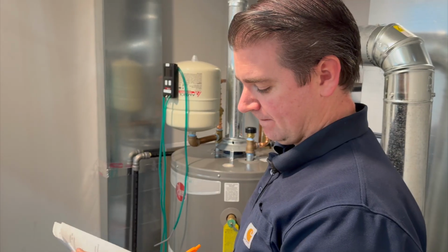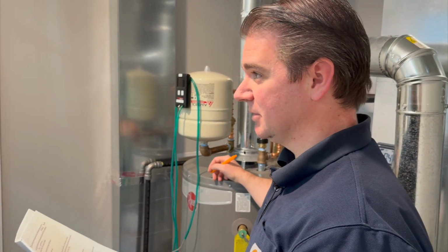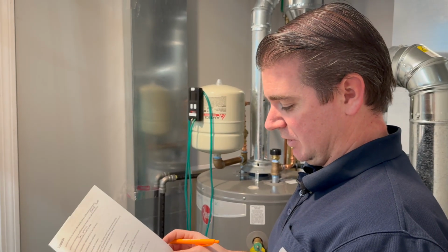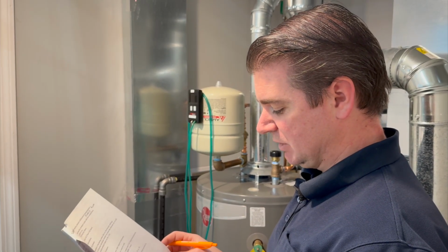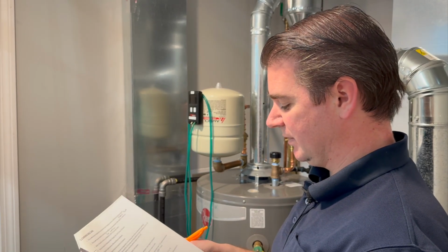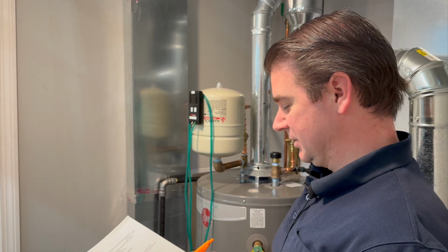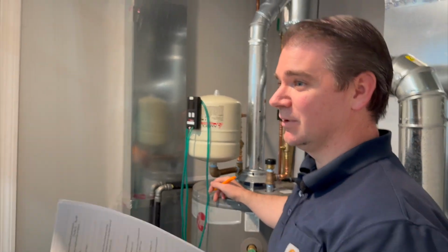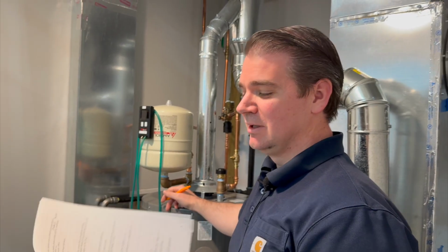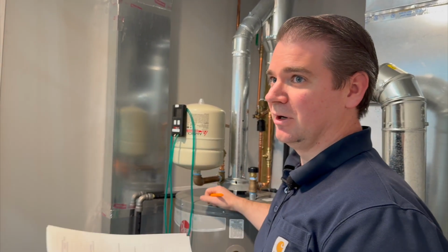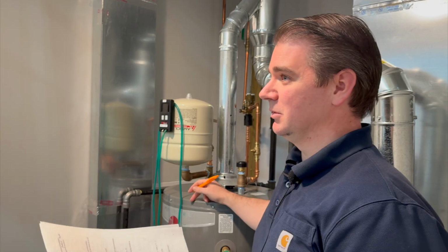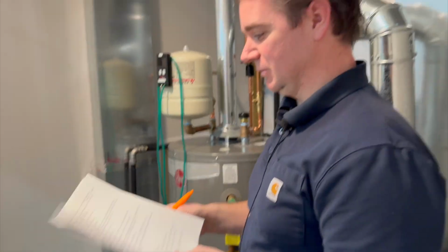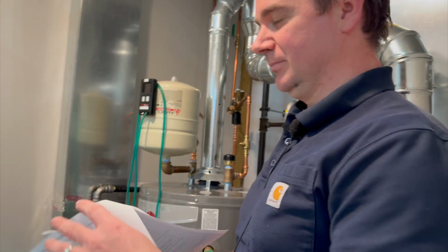And then number 10, discuss 3 potential sources of carbon monoxide in the home: water heater, furnace, oven. We already did number 2, 3, and 4. And discuss the procedure for measuring carbon monoxide in direct vented and power vented combustion appliances. So that would be with a PVC vent, right? That's going to go to the outside of the home. So if I can safely access where the vent terminates for the combustion analyzer, I'll just stick the probe right down the flue vent. If it's someplace where I can't get to, if it's up high, like on a 3rd floor, or like in an attic, or a roof, I won't be able to test it due to safety reasons. Bless you.